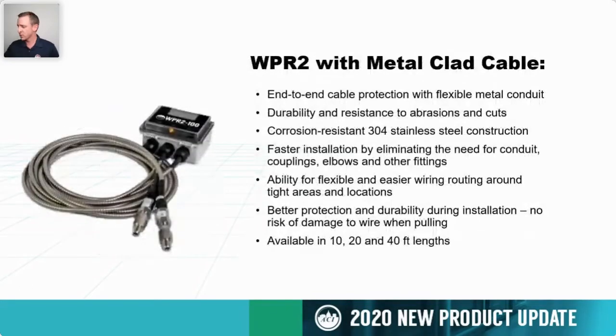The next new product that we'll talk about today is the new metal clad cable option for our wet-to-wet differential pressure transducer. This is a 304 stainless cable that encases the wire. The internal wires are run through the metal clad cable, so it provides end-to-end protection and eliminates the need for conduit couplings, fittings, and elbows.